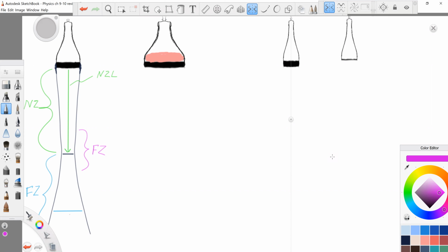So a pair of 6 megahertz probes, we know that they have this same thickness. All right, so why? Because they're 6 megahertz. That's the fundamental frequency anyway. And the determination of frequency comes from that thickness there. That thickness from here to here determines frequency. So both of these have the same thickness.